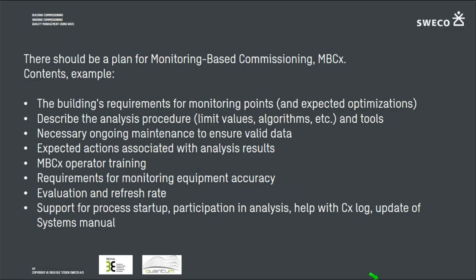There should be a plan for these ongoing and monitoring-based commissioning activities, including requirements for monitoring points. This is very much a requirement for the BMS system, since that's where you set up monitoring. If you don't get the monitoring points, neither the commissioning process nor the technical monitoring process has a chance.